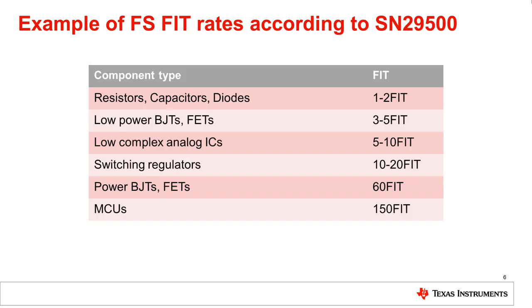The table below is an example of functional safety fit rates according to SN29500. For simple devices like resistors, capacitors, and diodes, the fit rate is very low, with a fit rate of 1 to 2. More complicated devices, like switching regulators, can have a fit rate in the range of 10 to 20. And some MCUs that are more complex could have a fit rate in the range of 150.